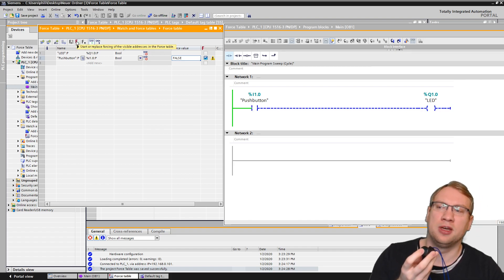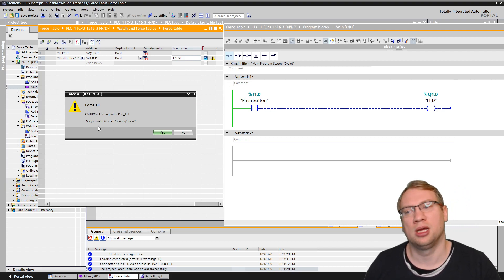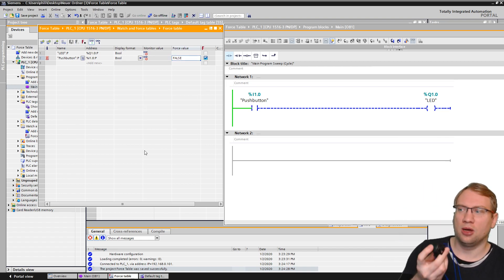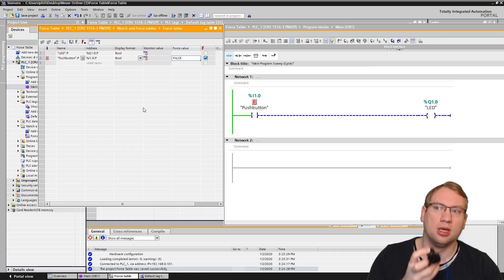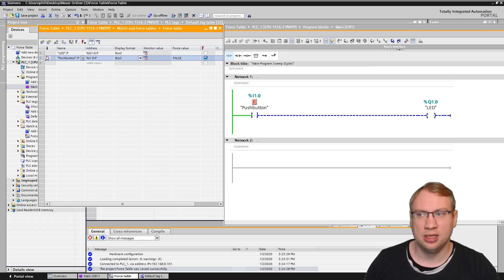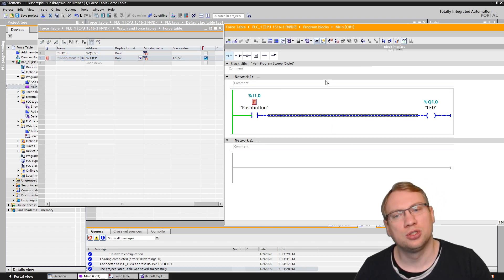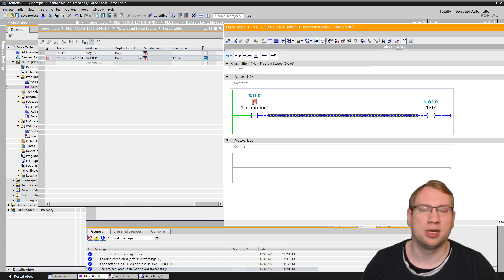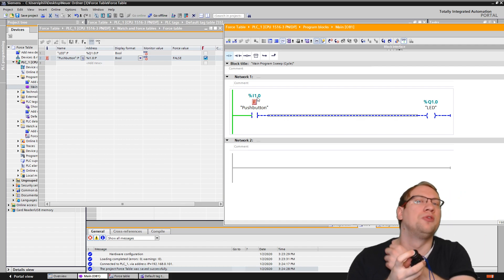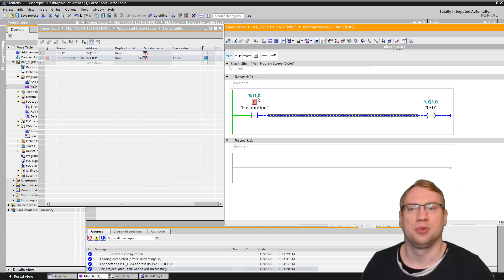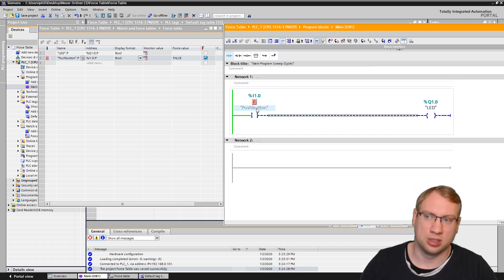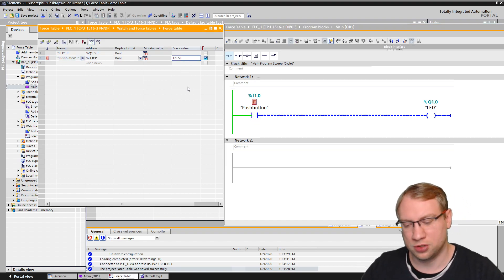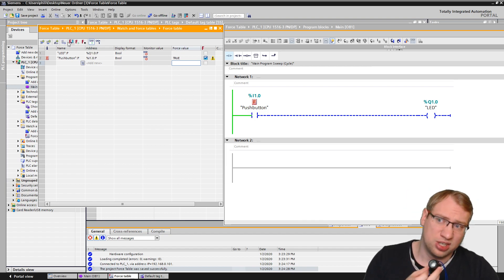If I now activate my force, it will ask me, caution, do you want to start forcing now? Yes, I want to. I know what I'm doing. And now if I press the button, nothing happens anymore. You see, nothing turns green because this one here, right now, you see it here. This one is being forced. This little F indicates, hey, this is right now forced. We can also see this here in our program. You see this F, this push button is being forced. Even if I press it, the physical input is overwritten. It's overwritten by the force table. All right, so the force is stronger than my button press here. It's for testing. Of course, it's stronger.